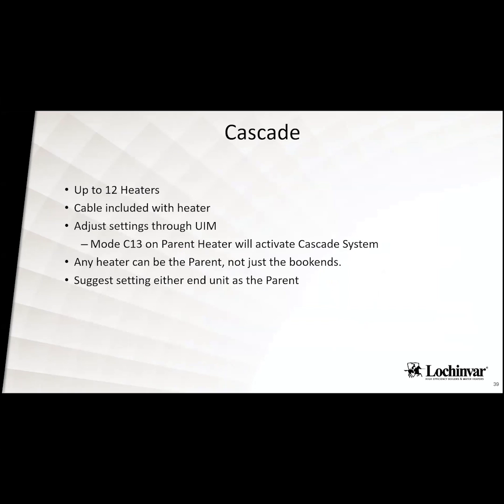So you can cascade 12 together. You can common vent them all too and common vent them out. Those cables again are included in there. Those settings that we looked at earlier, you would just activate and tell it which unit it is within that cascade. And any heater within that bank of units can be the parent unit, it doesn't need to be the one on the left or the one on the far right. So you can set it up however you want to on that.